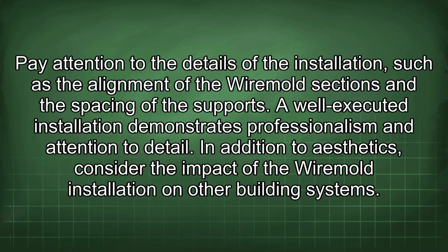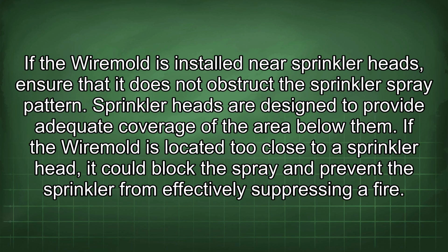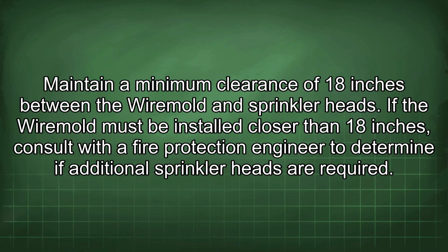In addition to aesthetics, consider the impact of the Wiremold installation on other building systems. If the Wiremold is installed near sprinkler heads, ensure that it does not obstruct the sprinkler spray pattern. Sprinkler heads are designed to provide adequate coverage of the area below them. If the Wiremold is located too close to a sprinkler head, it could block the spray and prevent the sprinkler from effectively suppressing a fire. Maintain a minimum clearance of 18 inches between the Wiremold and sprinkler heads. If the Wiremold must be installed closer than 18 inches, consult a fire protection engineer to determine if additional sprinkler heads are required.